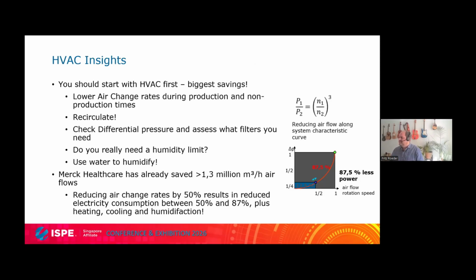And with HVAC, of course, lower air changes. This is the easiest, quickest part that brings a super saving. And I'm not only talking about production times, but also non-production times. If you have no shifts on the weekend or you have a maintenance shutdown, then you can bring down the air changes even further. Recirculate. Why do you need so much fresh air? 90% recirculation is no problem if you have proper HEPA filtration.